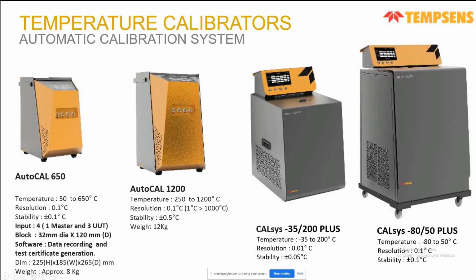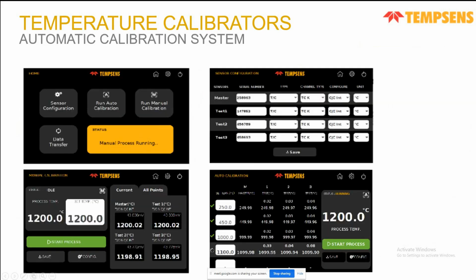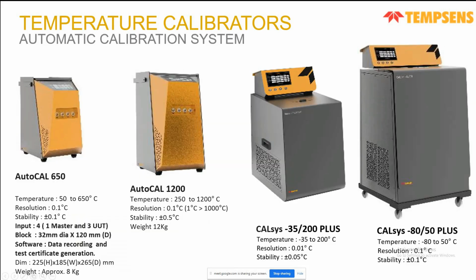This is a special system that we have designed. It's an automatic calibration system. So you don't have to note down the readings and do all these things. This will be done by the calibrator itself. As you can see here, each calibrator has got master, test 1, test 2 and test 3 probes. So what you do is, here is the well where you put your master and test, connect it over here, and you program.